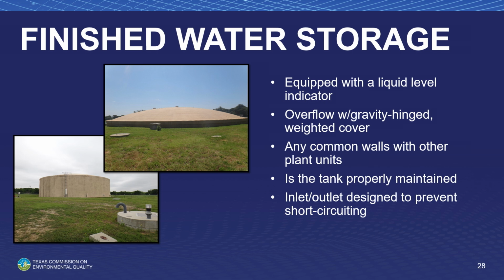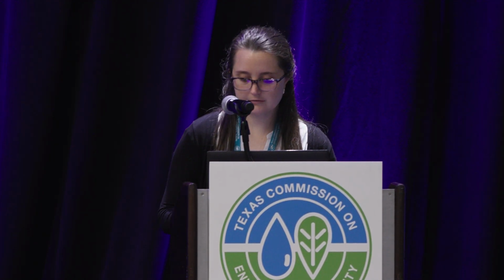Finished water storage. It's going to be very similar to any of the regular ground storage tanks. Are they equipped with the liquid level indicator? Is the overflow with a gravity hinged weighted cover? We're going to make sure there aren't any common walls with other plant units, and is it being properly maintained? And what's especially important at a surface water plant is that the inlet and outlet is designed to prevent short circuiting. A lot of times, the water storage of your plant is your clear well, which is where you're going to get a lot of your contact time with your CT study. So ensuring that you get good water flow through that tank is going to be important.